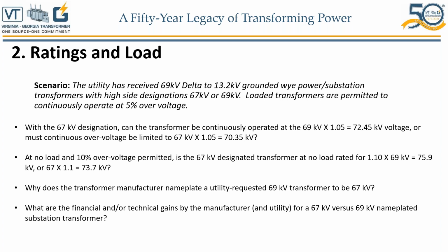And if your 69 kV is the nominal tap voltage, and you have 2 up and 2 down, then one tap up will be 2.5% more, another one 2.5% more, or vice versa. You can go down 2.5% less voltage, and then of course the minimum voltage tap will be 5% less than the nominal system voltage. And in the same C57.12.00, table 3 for class 1 and table 4 for class 2 clearly define what the nominal system voltage and maximum operating system voltages are.